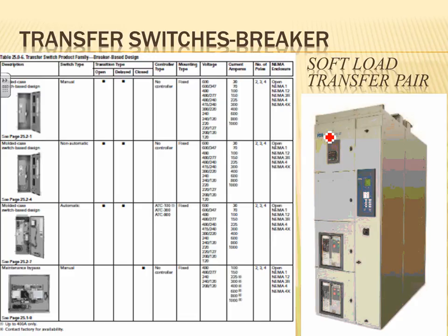If it's closed transition, you close both of them to the two utilities momentarily, not forever though, so not really paralleling, and then you drop the one that you want to drop. So these are two technologies. Again, they call it soft load transfer. If you're doing breakers, most likely you have closed transition. Closed transition. Any comments, guys?